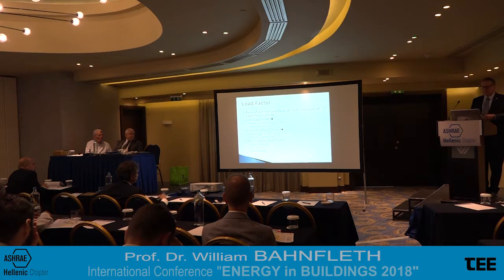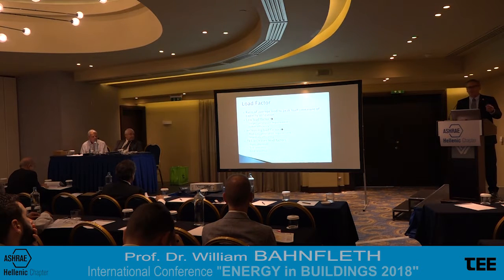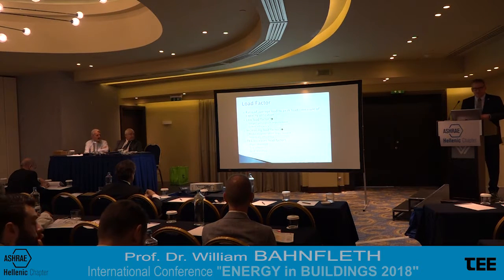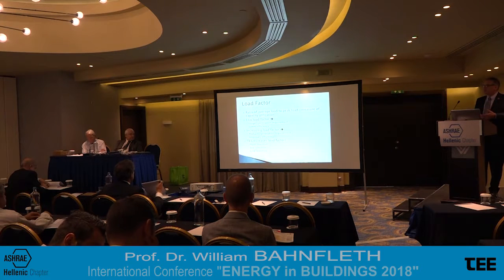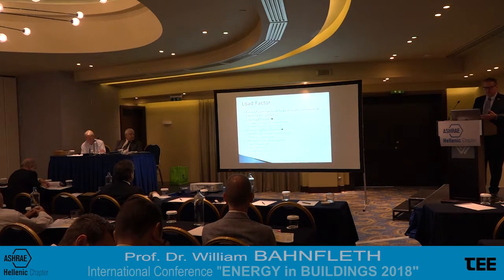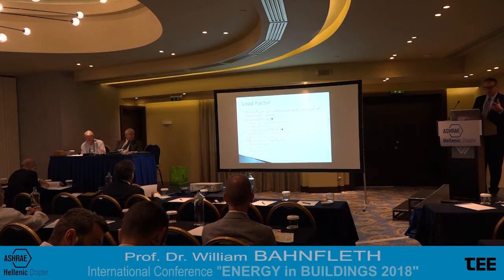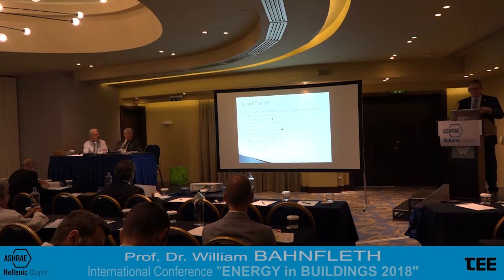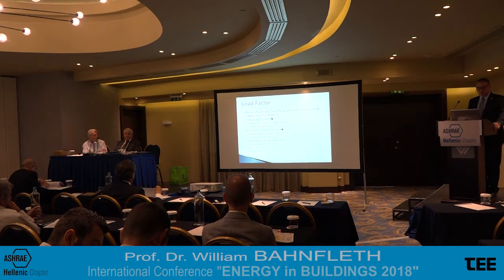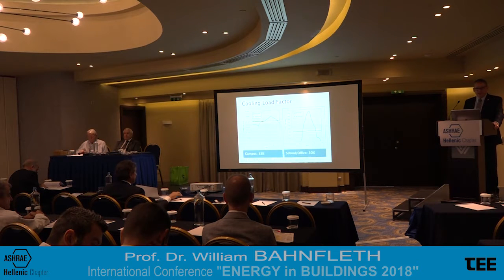Thermal storage can increase load factors for the cooling plant itself. So locally, the thermal load factor can increase the load factor for the site electricity, because typically there's a lot of electric power going into cooling systems, and that aggregates to a beneficial effect on the load factor of the grid. So the building is connected all the way back to the point where power is generated.